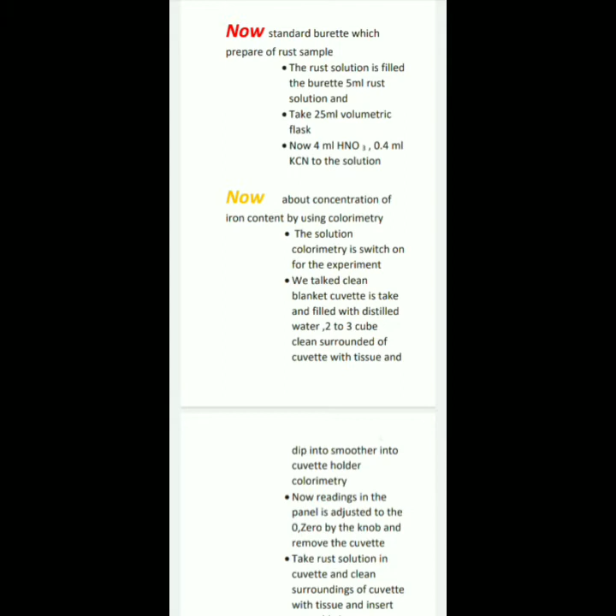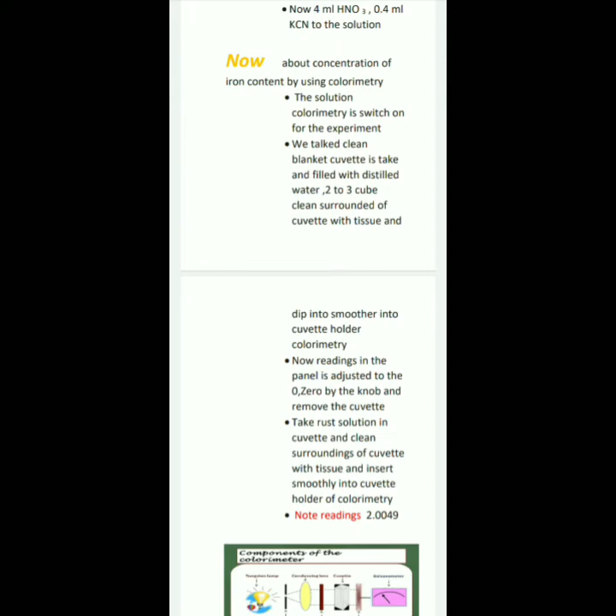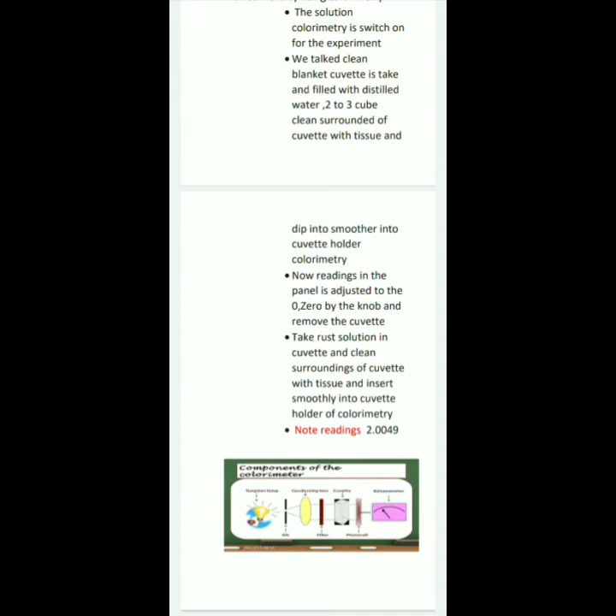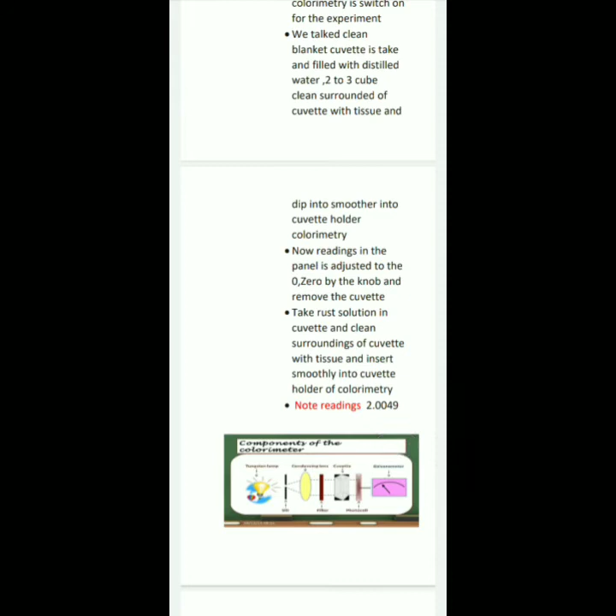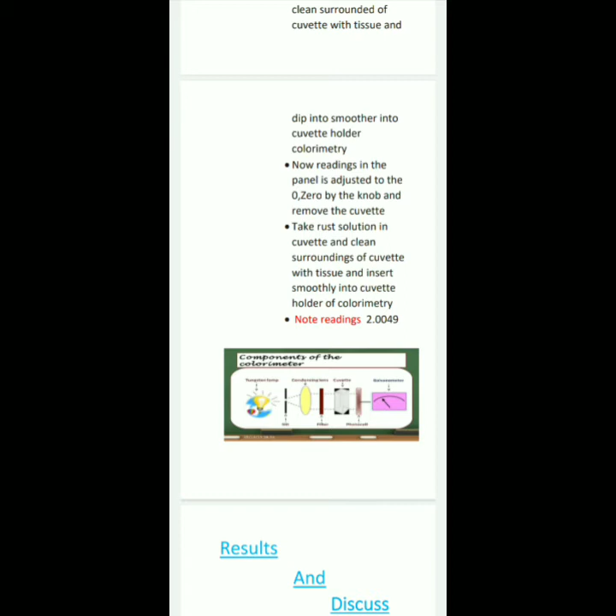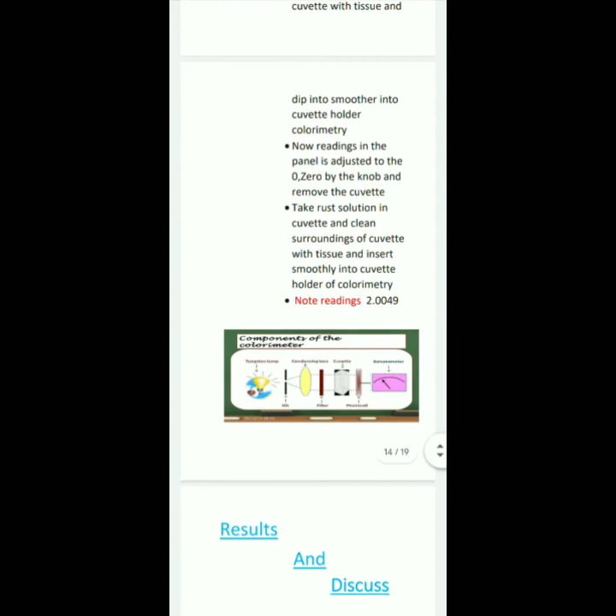Now we are observing the concentration of iron content using colorimetry. We switch on the colorimeter for the experiment. Now we take a clean cuvette and fill it with distilled water. Clean the surroundings of the cuvette with tissue and insert it smoothly into the cuvette holder of the colorimeter. Now the reading on this panel is adjusted to 0 by the knob, and we remove the cuvette. Take the rust solution in the cuvette, clean the surroundings with tissue and insert the cuvette smoothly into the cuvette holder. Now we get the reading 2.0049.